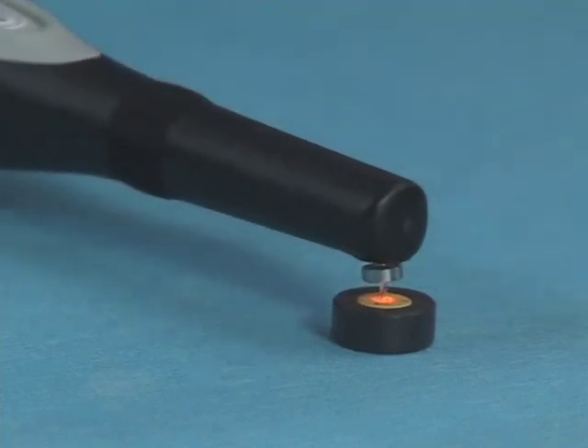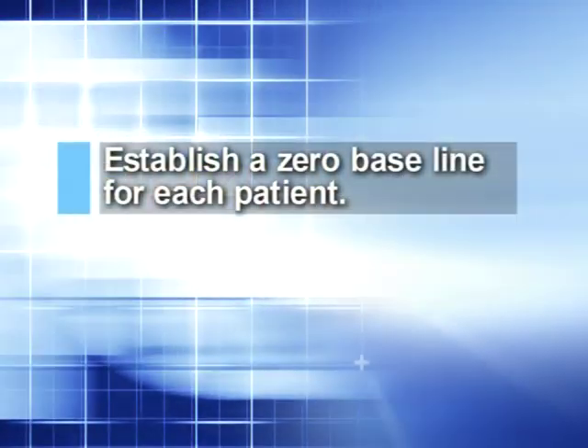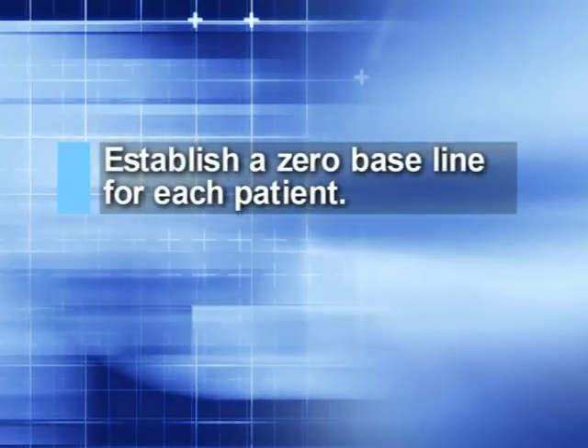For the DIAGNodent pen, hold the tip in the air and press the menu button, immediately followed by the enter button. When the tone starts, gently place the probe tip on the center of the calibration disc. When the audible tone stops, the calibration sequence is complete and the unit is ready to use. Establish a zero baseline for each patient. Because people have different levels of naturally occurring fluorescence in their healthy teeth, a baseline must be set for each patient. This is particularly important when suspect tooth sites are re-examined at various time intervals.